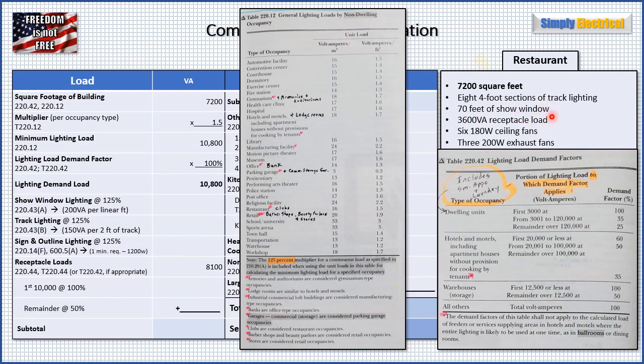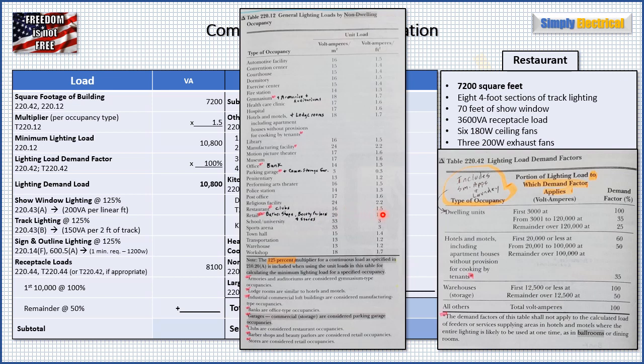We have all our data and we're going to apply it to our table, starting in the left column with the square footage: 7,200 square feet. I have the code references here for each step. Then we go to Table 220.12 to find our multiplier — general lighting loads by non-dwelling occupancy. Going through the occupancy types, we find 'restaurant' listed exactly, giving us a 1.5 VA per square foot multiplier. So 7,200 times 1.5 comes out to 10,800 VA, and that is our minimum lighting load.